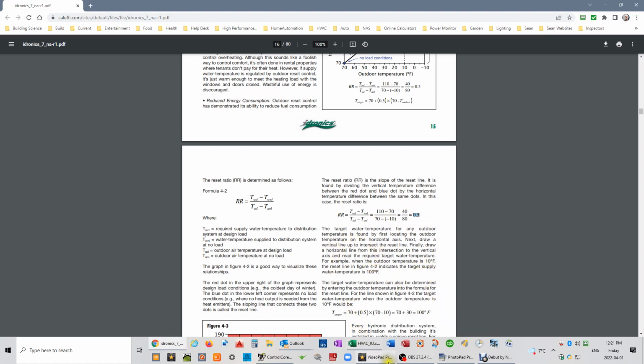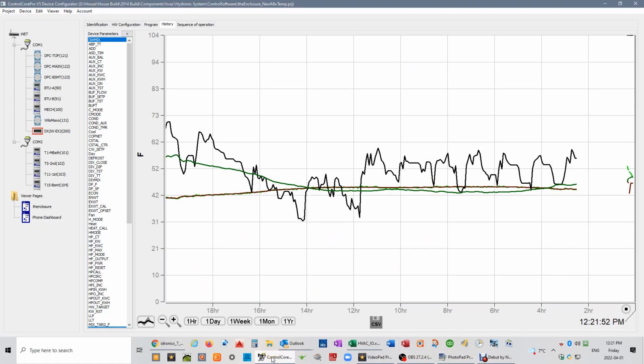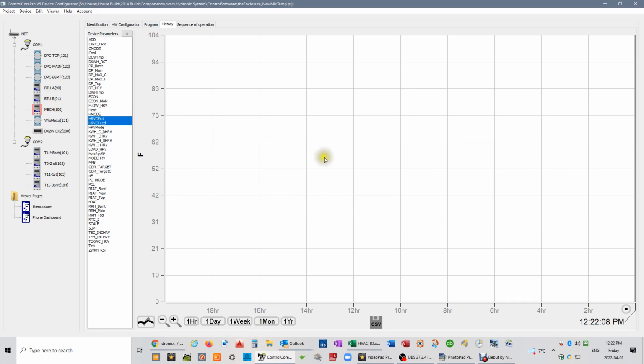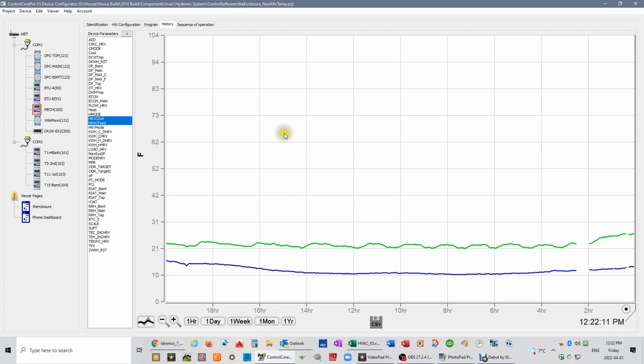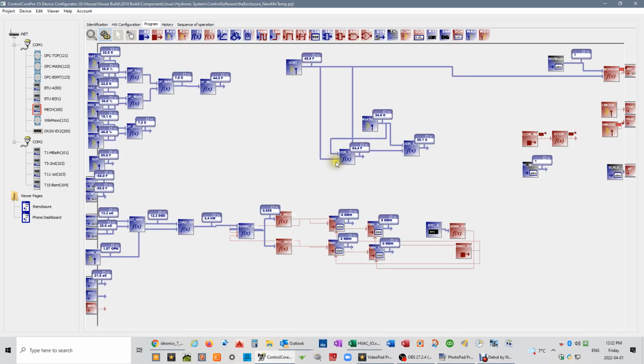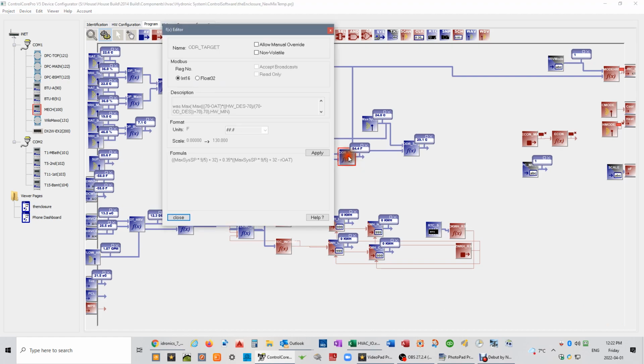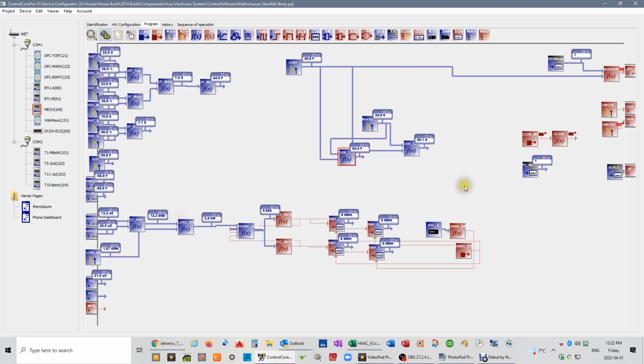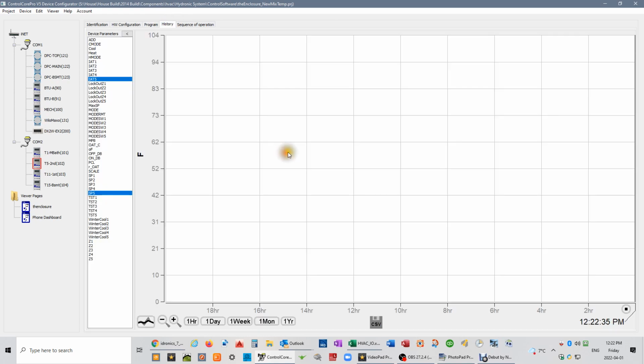I figured out my reset ratio not based on what I calculated in my design, because it looks like I may have under designed, but based on just how the system was performing, I increased the reset ratio over time until the system was providing the heat needed by the house. And so it made it really easy to change. I started out at 0.3 and I've gone up to now 0.35. And now I find that I am able to meet all of the set points.